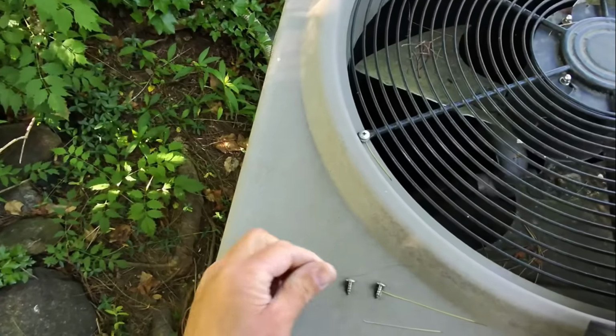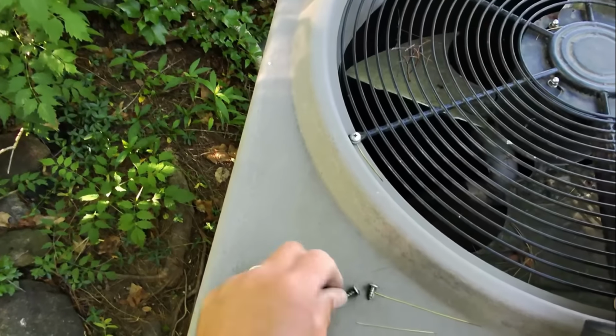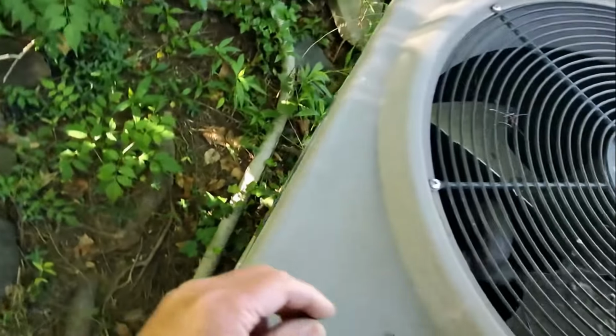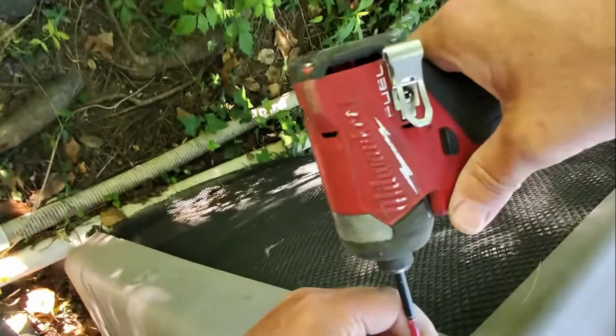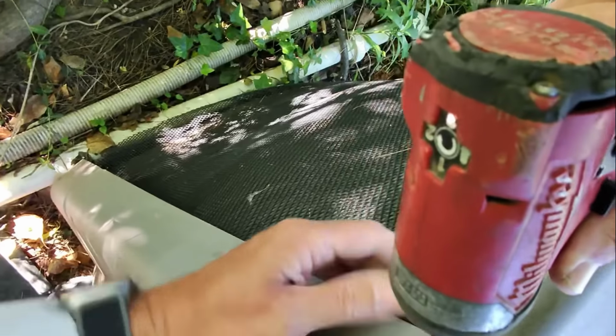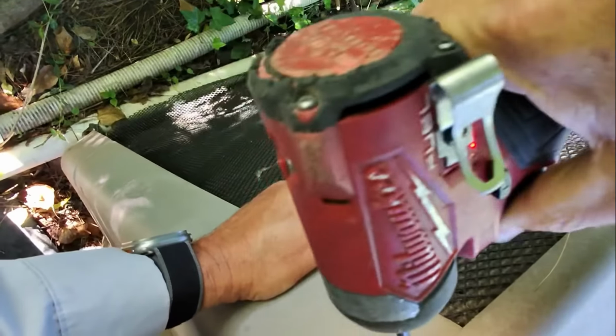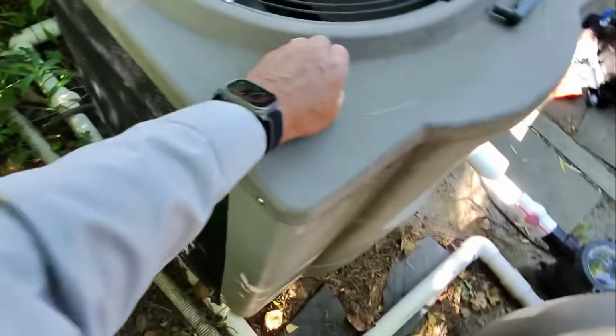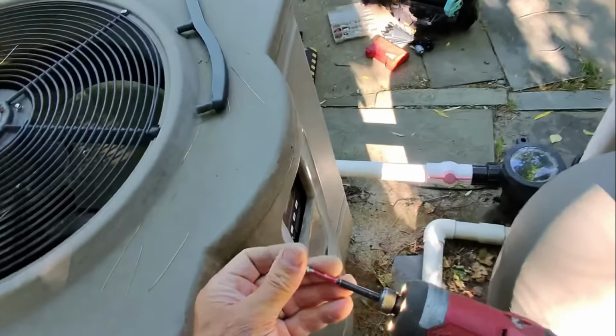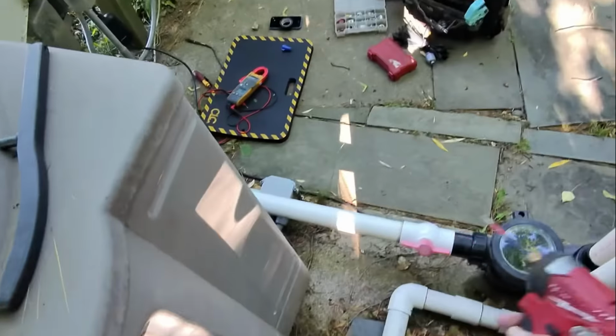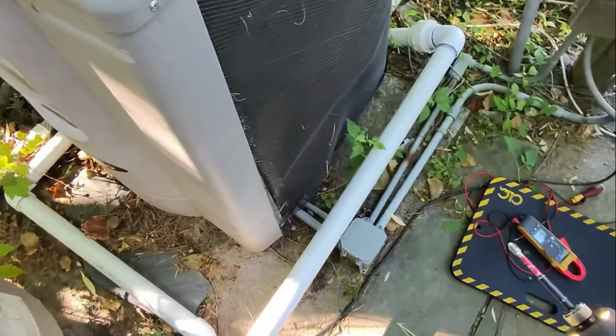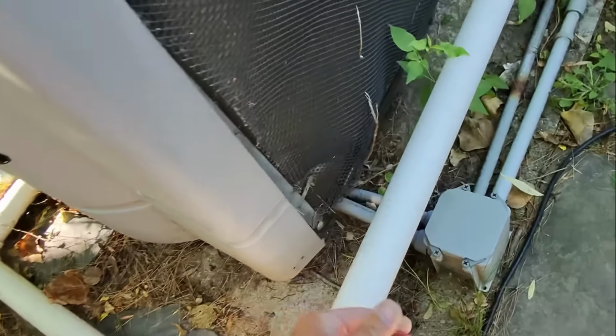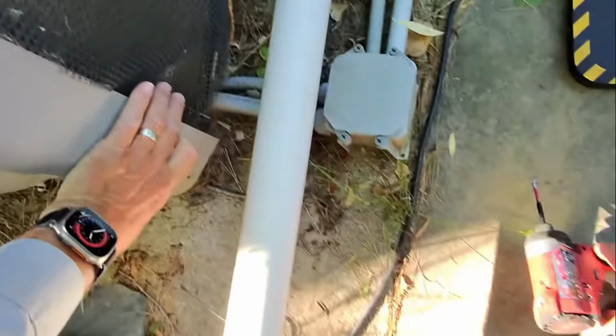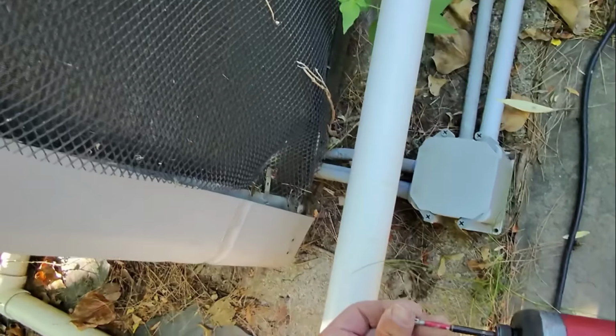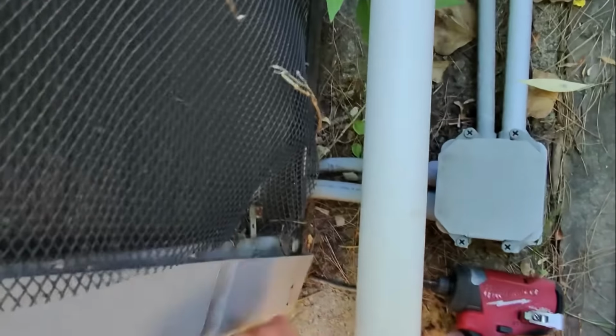And by the way, if you use the wrong screw, like if I use this long screw down there, I'm going to put a hole in the coil. This happened to me before, folks - I kid you not, it has happened to me before. So be careful, don't do what I did, and spent hours repairing a leak from a screw I put into the unit.